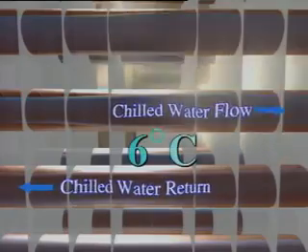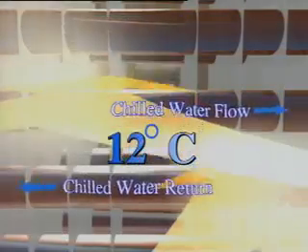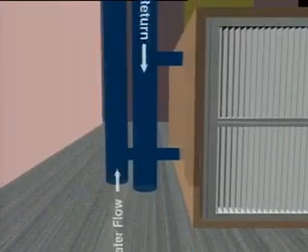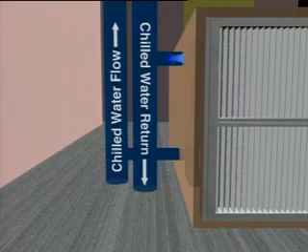The heat absorbed by the chilled water raises its temperature from 6 degrees Celsius to around 12 degrees Celsius. The 12 degrees Celsius chilled water, after leaving the cooling coil, is returned to the chiller at the central plant room.